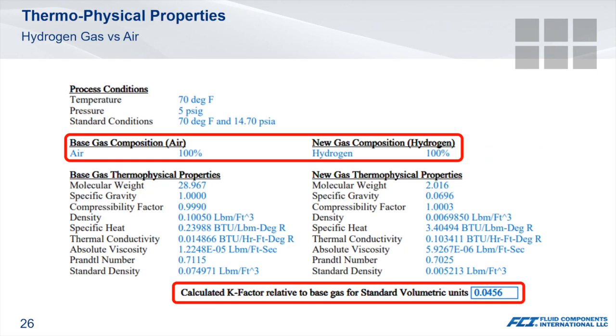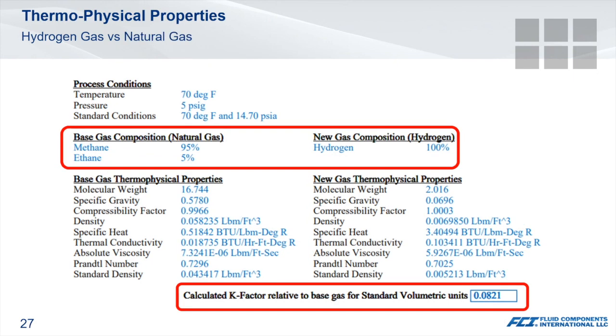Let's further illustrate why an air equivalency for hydrogen flow measurement is not a good practice. The difference in thermophysical properties of the two gases are extreme. If using a linear correction factor, the results would be highly questionable given the equivalent flow of hydrogen is only 4.56% that of air. Not only does this type of correction impact flow meter performance, it also greatly limits the measurable flow range. Using a hydrocarbon such as natural gas for an equivalency media is not much better. The correction factor is still under 10%. This is just more confirmation that actual gas calibrations are necessary to ensure flow meter performance.